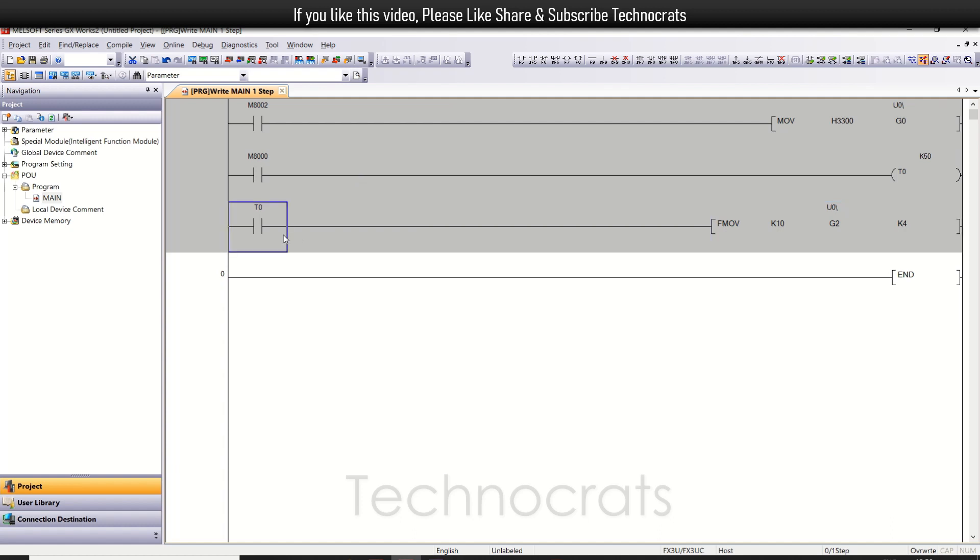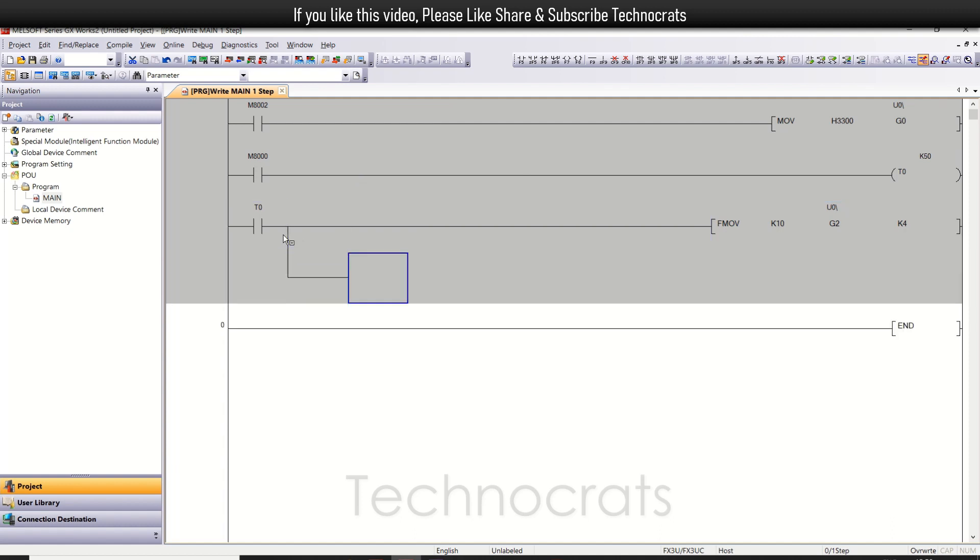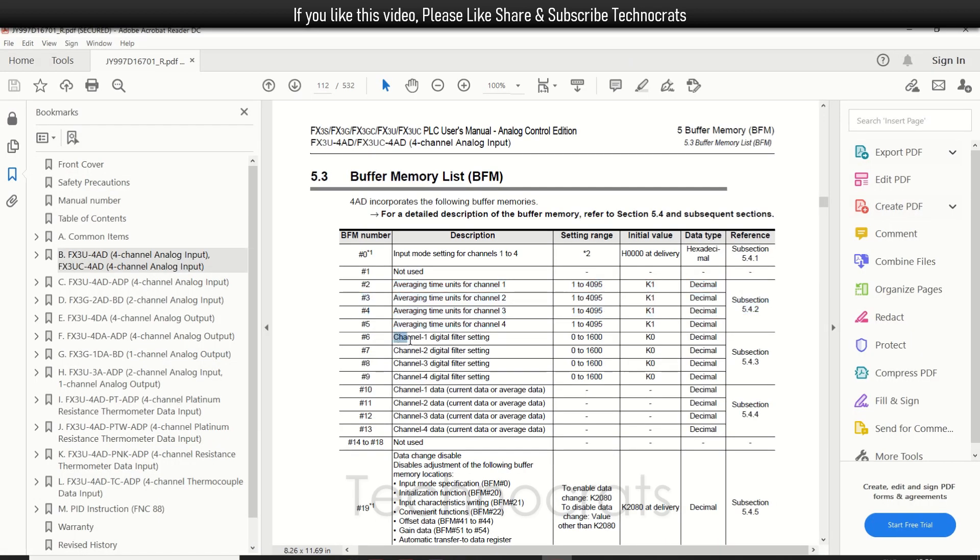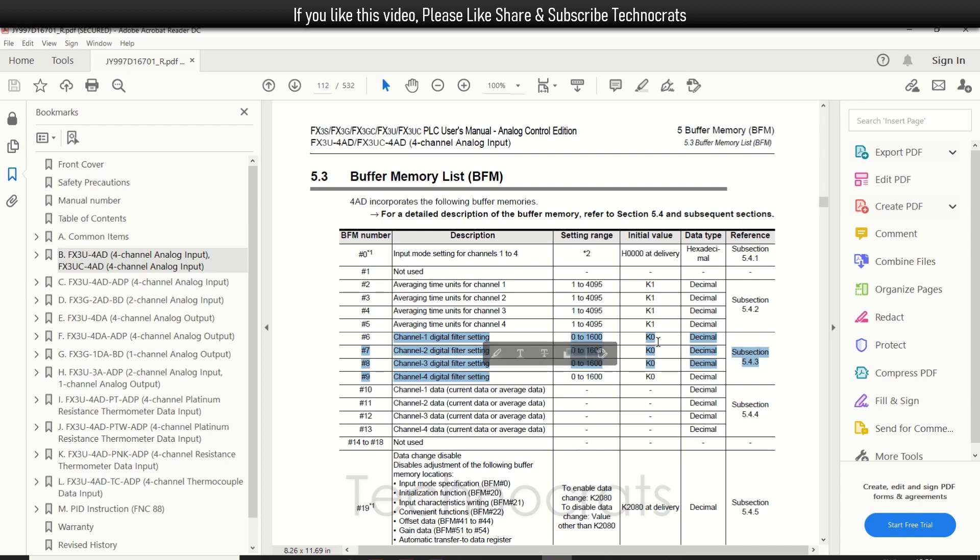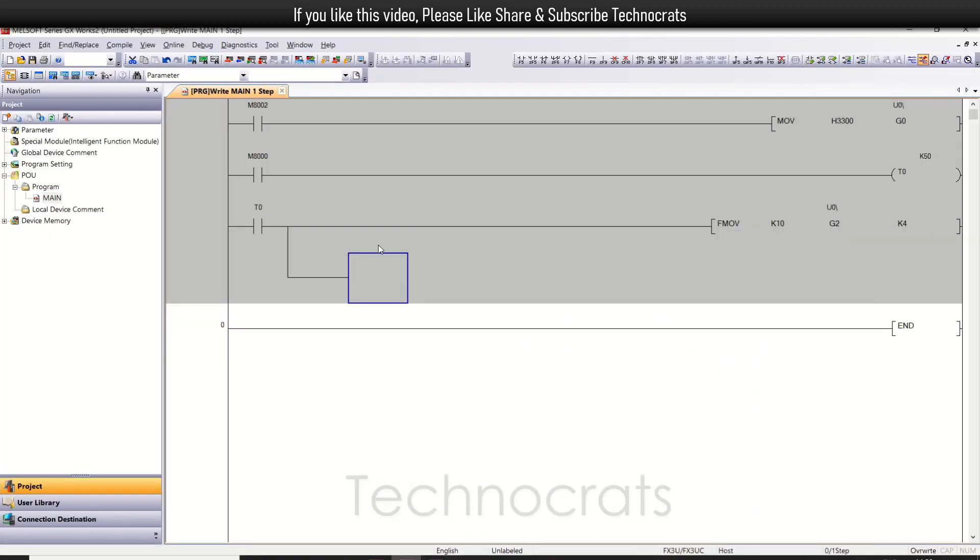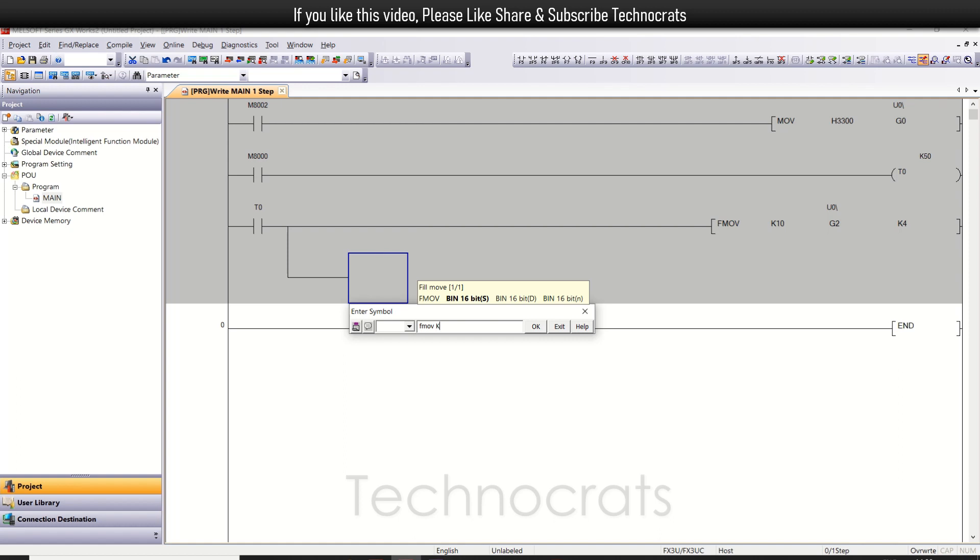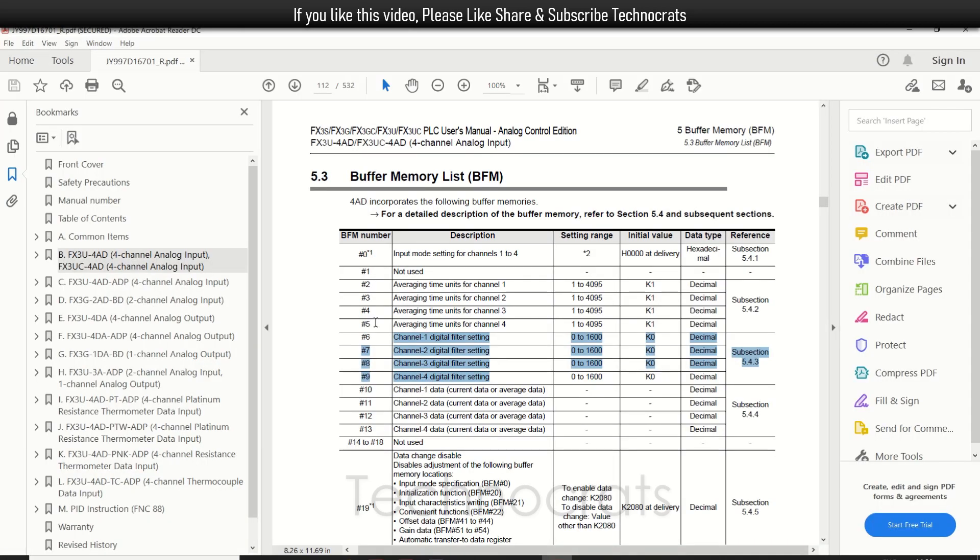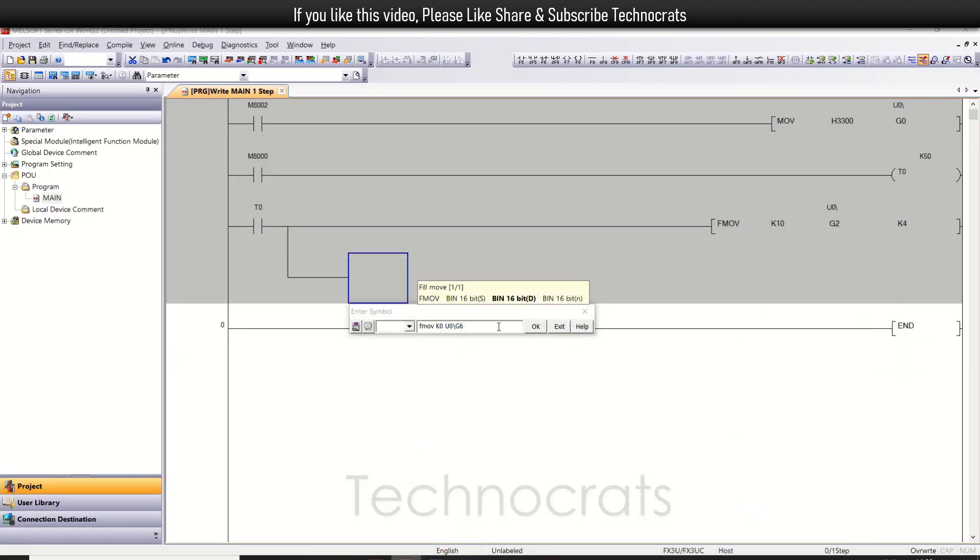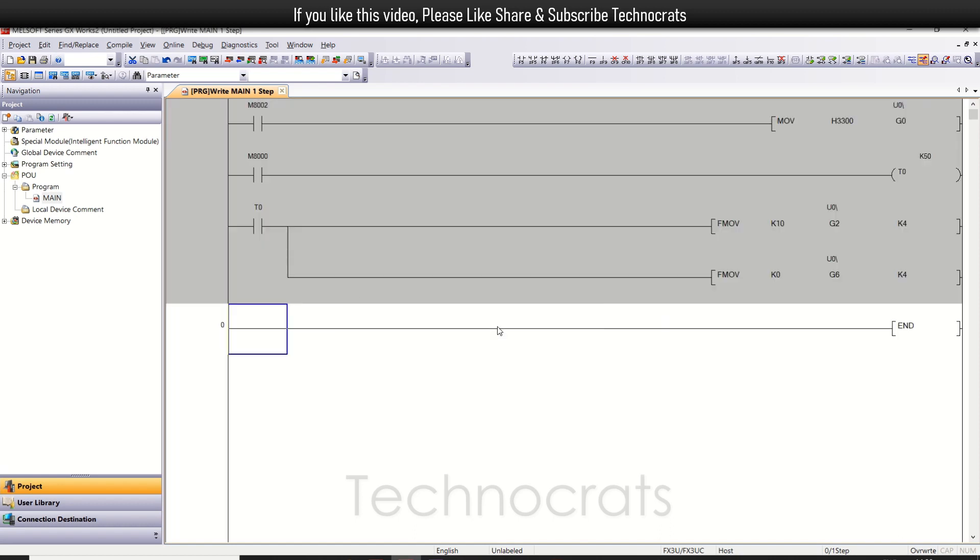Now let me insert one more rung. This is for the digital filter, which is from channel 1 to 4. Buffers 6, 7, 8, and 9. I will bypass this. I will use K0 here, which is also the initial value. So I will use FMOVE K0 to U0\G from 6, 7, 8, 9. Number of values is 4, K4. So 0 will move to U0\G6, 7, 8, and 9, which is for the digital filter.